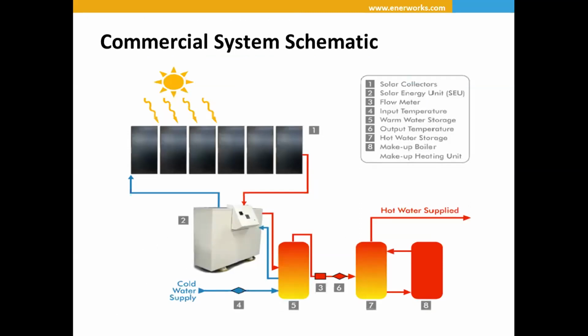This is an example of a typical system. Most systems are going to be simple preheat systems, where domestic water goes into the tank, and then we're drawing from the tank and just recirculating through the solar system. We're going to heat the tank up to whatever temperature we can get. Sometimes we'll be able to heat it up to 140, sometimes to 160. Some days, if it's cloudy, we might only add 20 degrees to the tank. So if the incoming water temperature is 60, we might only get it up to 80. But any energy we add to that is energy that your conventional heater, whether it's electric or gas, doesn't have to heat up. So you're saving that energy every day, regardless of the amount.